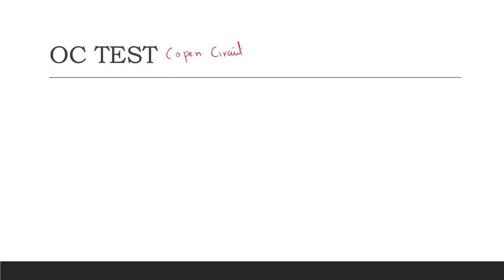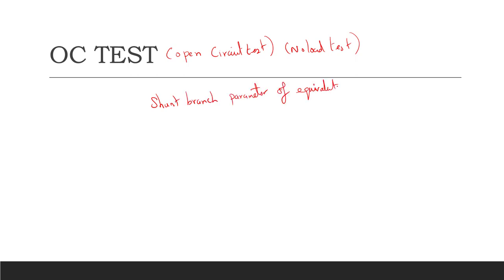We are going to discuss initially what is OC test. OC test is nothing but open circuit test, also called the no-load test. This test will be conducted when the load is zero. In OC test we are going to find out the corresponding shunt branch parameter of the equivalent circuit, and also we are going to find out the core losses of the system.